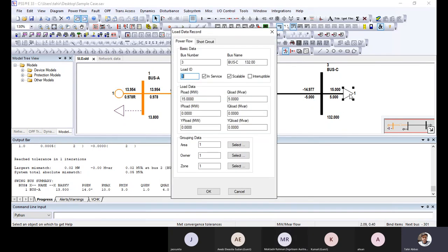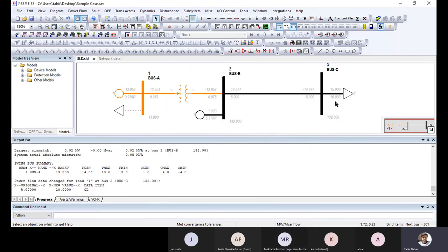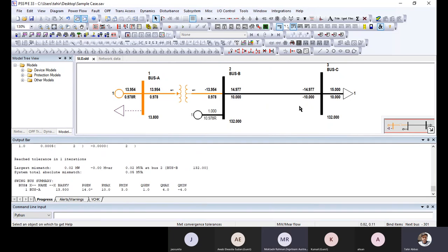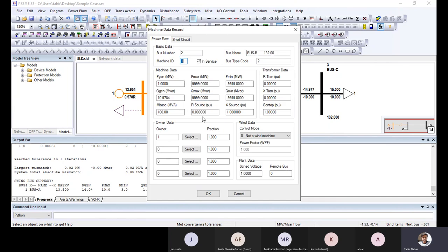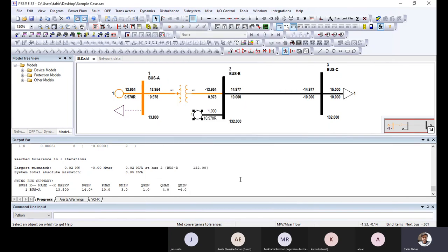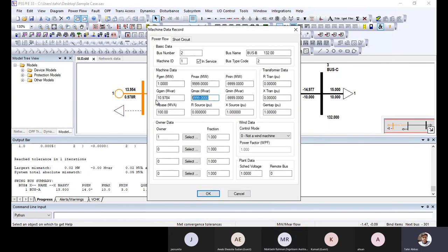I'm increasing the reactive power of the load for the system. I am adding 10 megawatt. Now you will see that the 10 megawatt reactive power is supplied by the swing. Okay, I'm switching it off. Now we can supply the added 2 megawatt here.